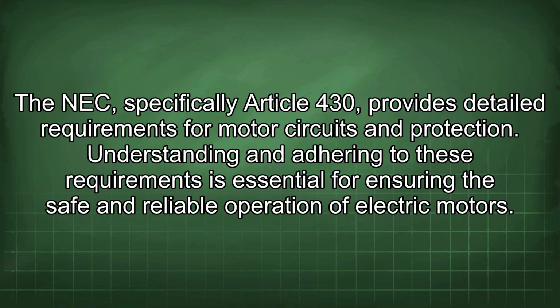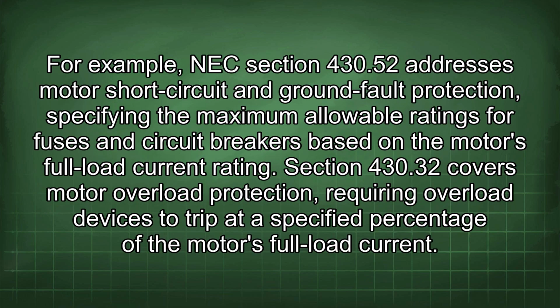The NEC, specifically Article 430, provides detailed requirements for motor circuits and protection. Understanding and adhering to these requirements is essential for ensuring the safe and reliable operation of electric motors. For example, NEC Section 430.52 addresses motor short circuit and ground fault protection, specifying the maximum allowable ratings for fuses and circuit breakers based on the motor's full load current rating.